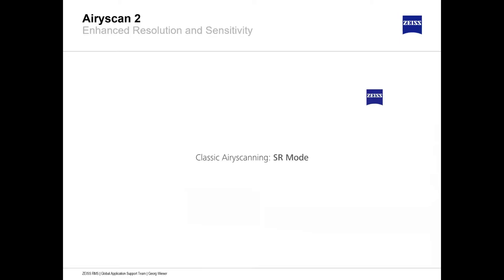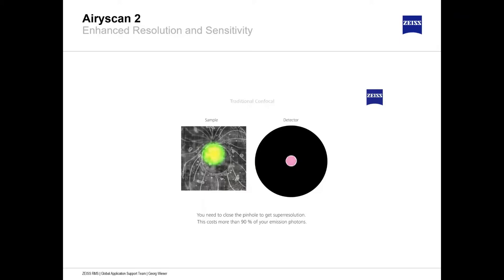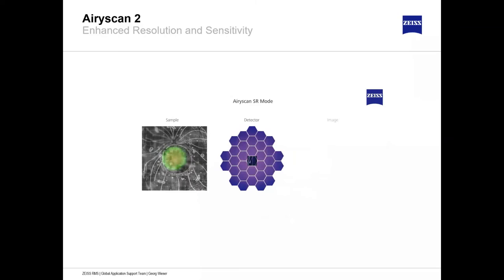This animation shows why Airyscan increases resolution and signal-to-noise ratio. In traditional confocal, a diffraction-limited laser spot scans the sample and you must close the pinhole for super resolution, which costs many photons. With Airyscan 2, all photons of 1.25 Airy units are detected, the spatial information is extracted, and a single super resolution image is calculated — repeated for every pixel, resulting in a complete super resolution image.